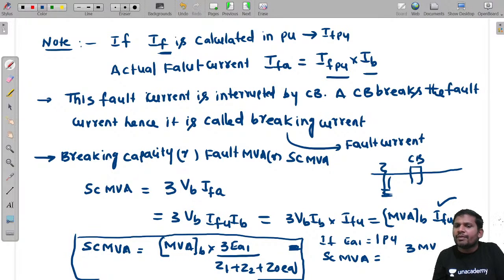Short circuit MVA is 3 into MVA base by Z1 plus Z2 plus Z0. If reactance is given, sir, you write X1 plus X2 plus X0 equivalent. Here I am writing in terms of impedances, sir. If it is given in terms of reactance, you replace that one. Understood, sir? That is short circuit MVA. Very important notes are all these. You please concentrate.